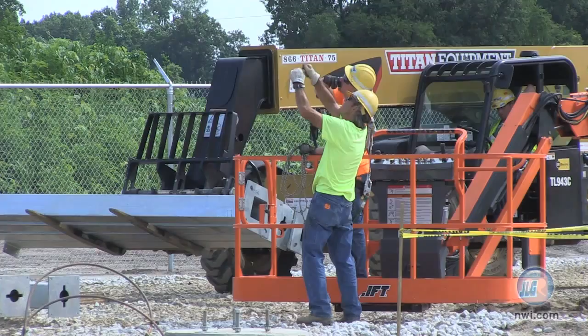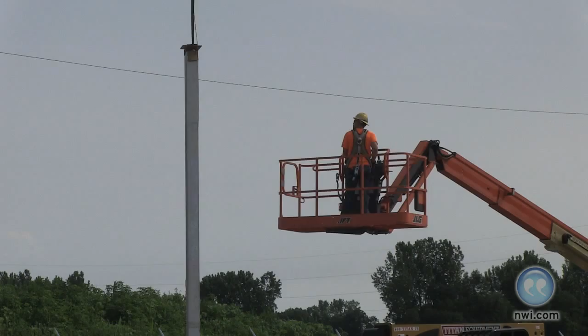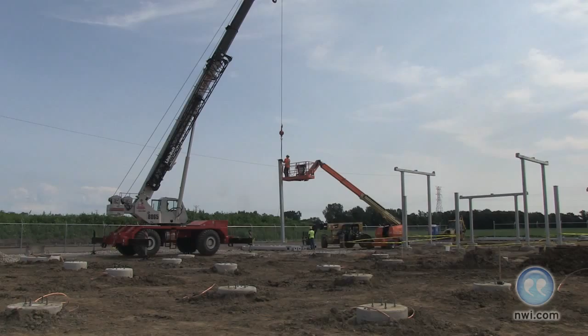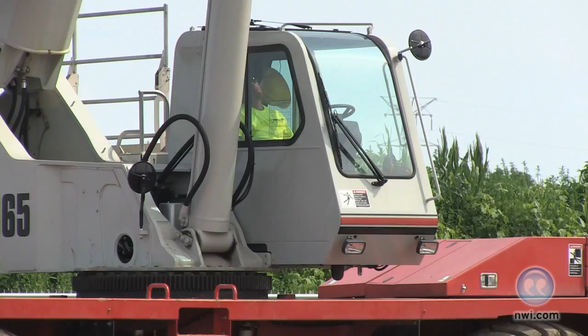There's quite a bit of additional work going on, so what you don't see at just the footprint of this substation is the feeder lines coming into this sub. We have new communication cable being strung that will come in here to help the relaying. Beyond where we're standing today, we also have a number of other electric side projects going on at other substations to modernize them, from a protection scheme standpoint, new transformers, some new breakers and switches, those types of things replacing aged equipment.